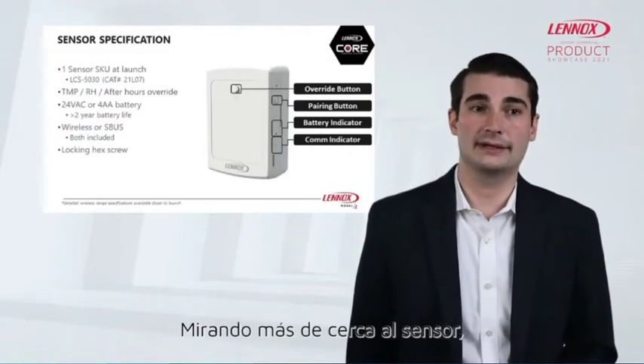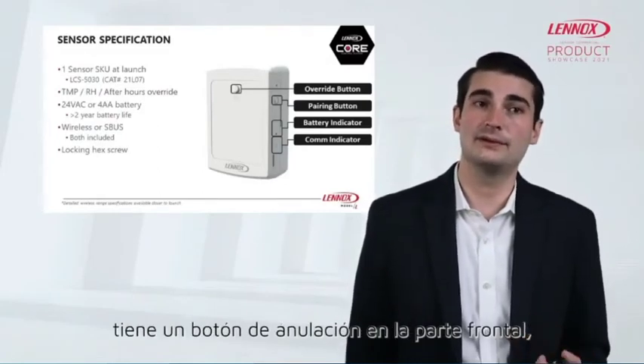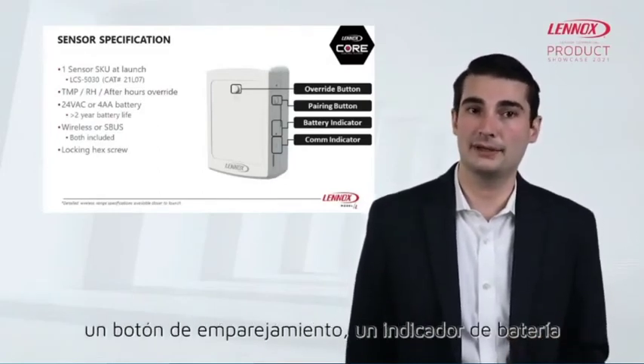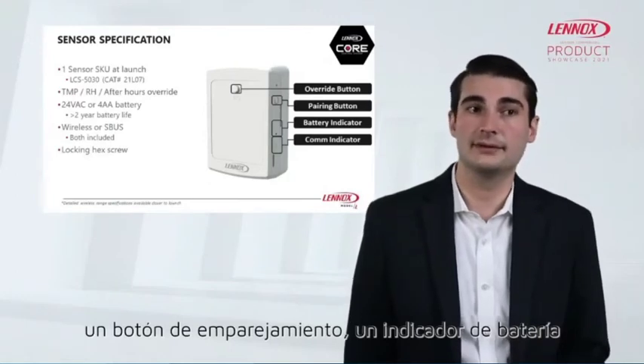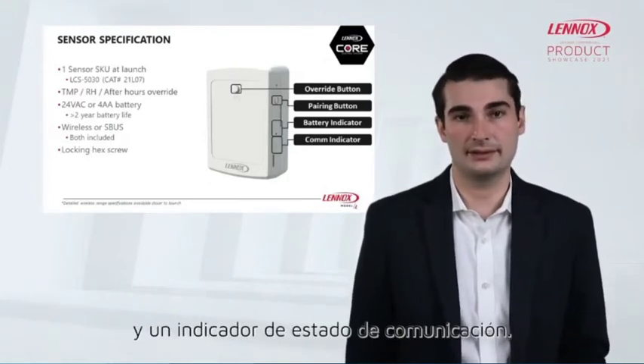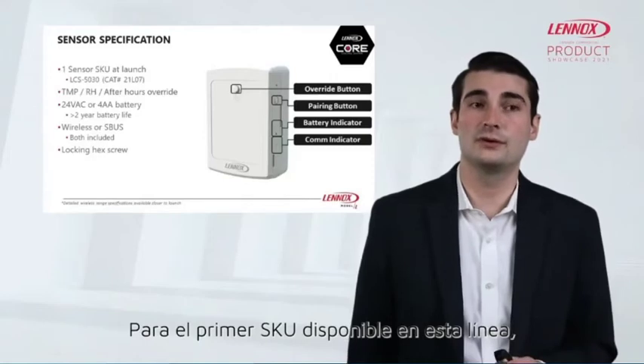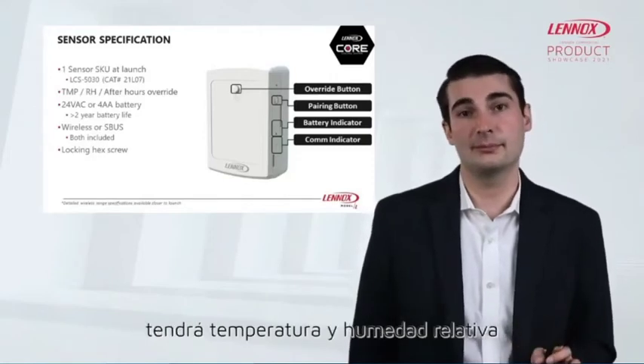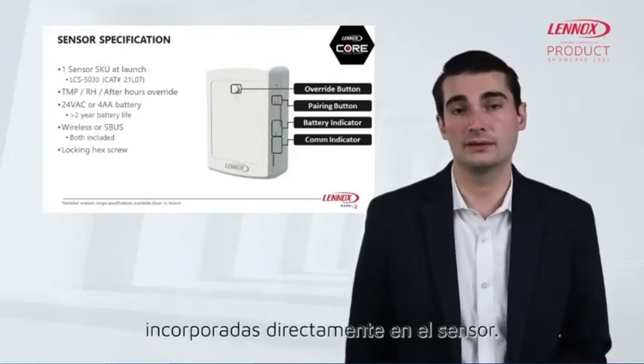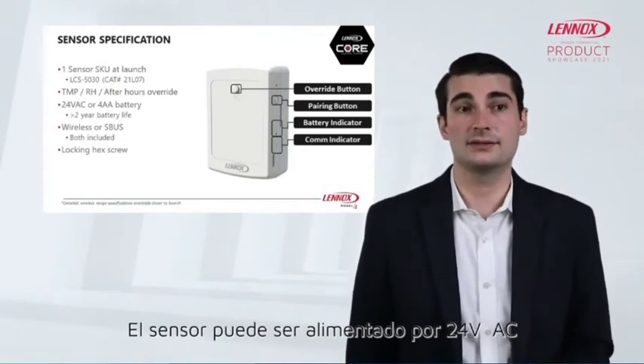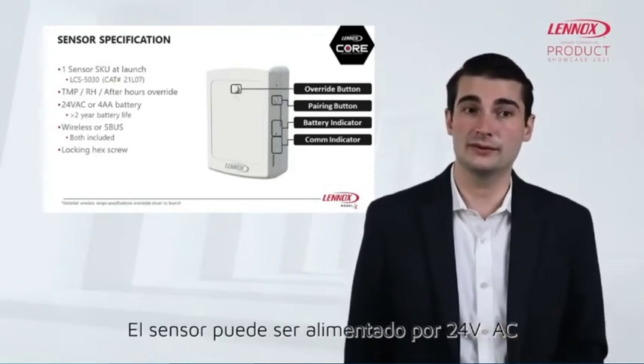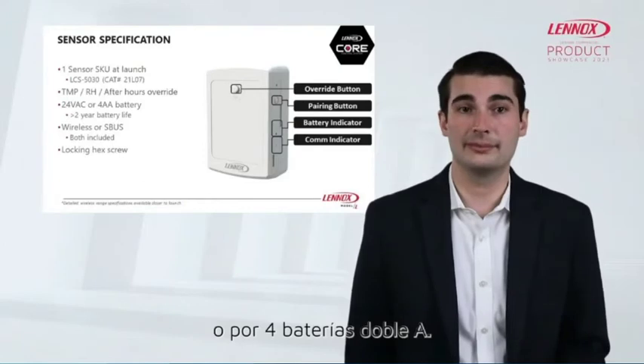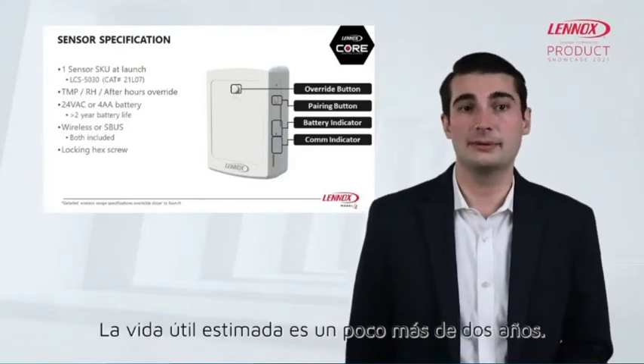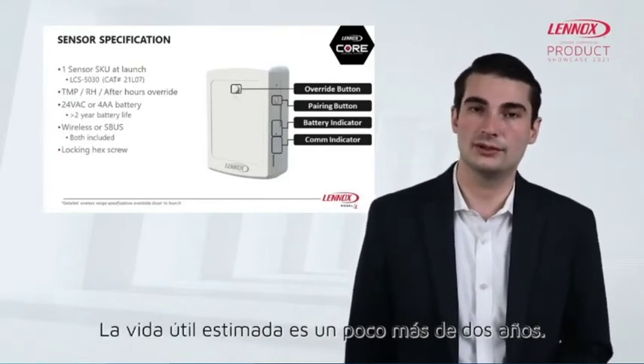Taking a closer look at the sensor, it has a front-mounted override button, a pairing button, a battery indicator, and a communication status indicator. For the first SKU available in this line, it will have temperature and relative humidity built directly into the sensor. This sensor can be powered by either 24 volts AC or 4 AA batteries. On battery, the typical estimated life is just over 2 years.